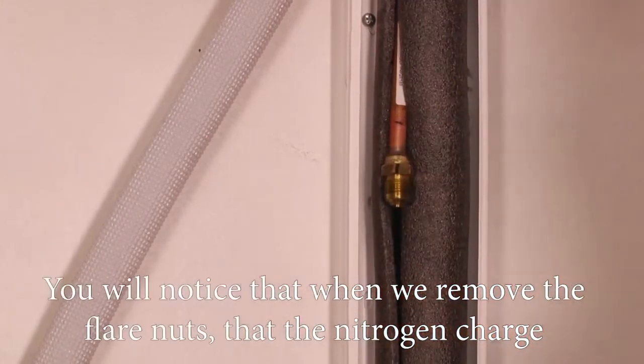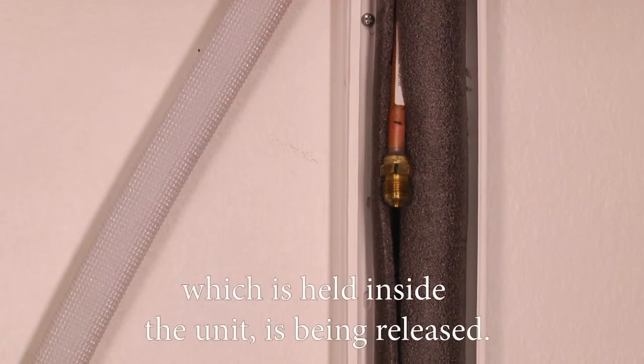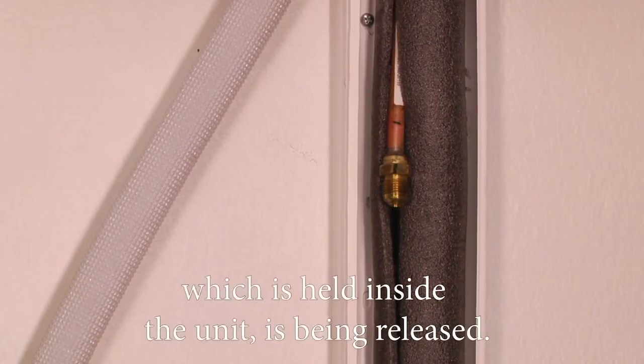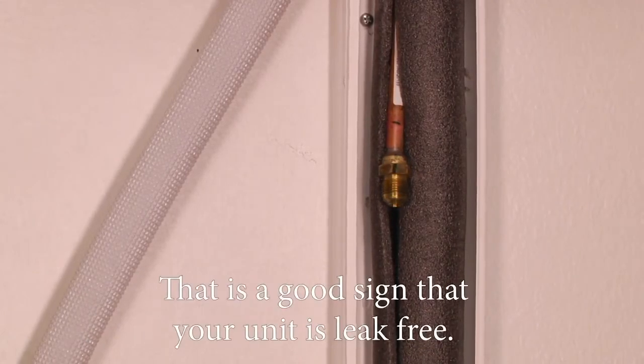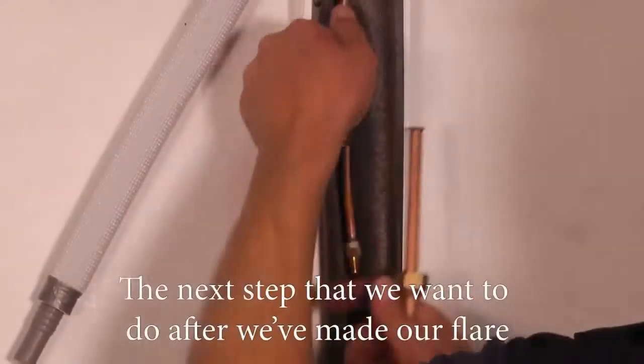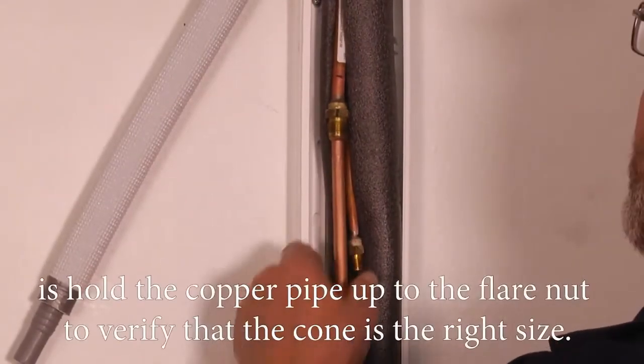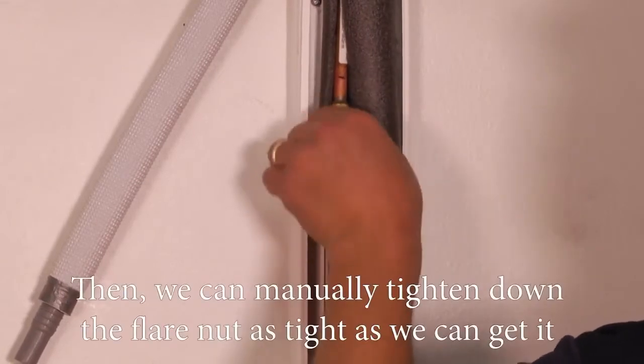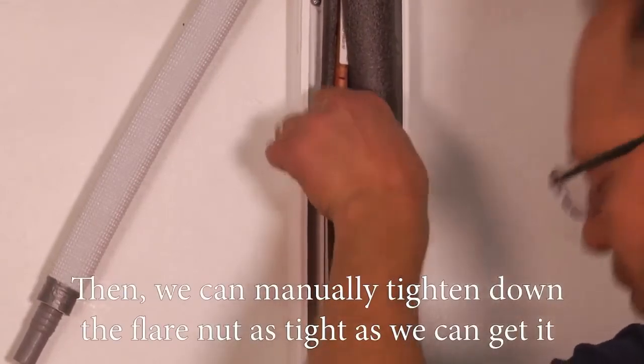You'll notice when we remove the flare nuts that the nitrogen charge which is held inside the unit is being released. That's a good sign that your unit is leak-free. So the next step that we want to do after we've made our flare is hold the copper pipe up to the flare nut to verify that the cone's the right size. Then we can manually tighten down the flare nut as tight as we can get it.